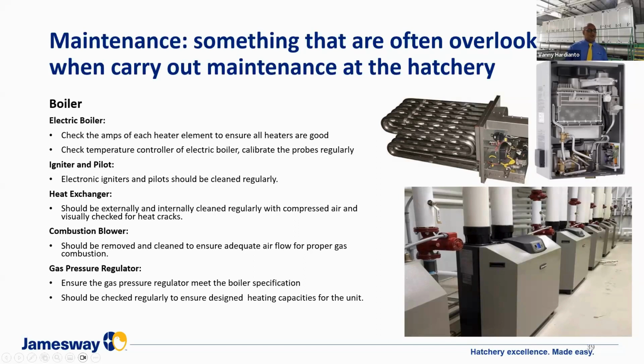With the electric boiler, you have to ensure all heater elements work by checking the amperes. The temperature controller is also very important for the electric boiler. So when the temperature controller fails, the boiler will not work. With the gas boiler, you have to check the igniter and pilot, the heat exchanger, the combustion blower, and also the gas pressure regulator. When one of these functions fails, the gas boiler will not work. Usually, each boiler manufacturer gives the gas pressure specification, and you have to follow the specification.